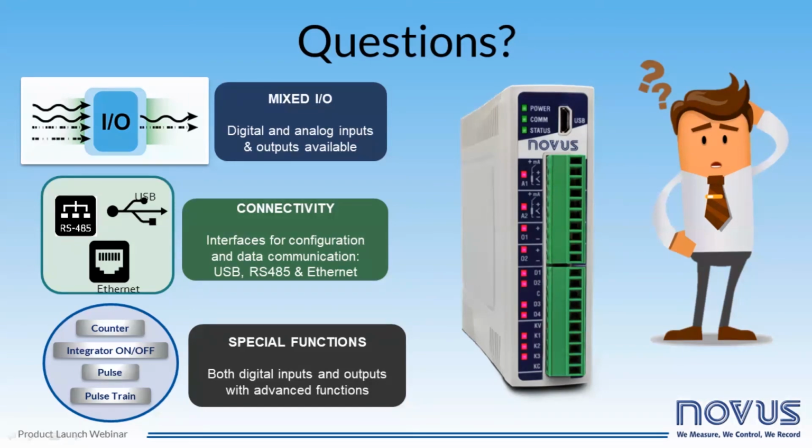Another question, can this device be connected with other devices, for example, PID controllers, on the RS-485 interface? Yes, it's possible, but in this case, there is no RTU master. No PID controller is master, and also DigiRail Connect is not master. But the DigiRail Connect can be connected through a host on the Ethernet, and then the host can access the other PID controller through the RS-485 network, as a gateway. So the host can read either DigiRail Connect or the PID controller, okay?